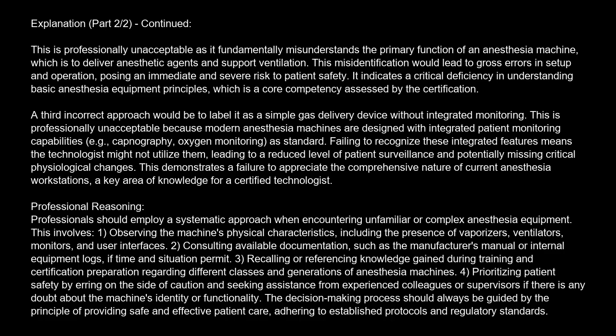integrated monitoring. This is professionally unacceptable because modern anesthesia machines are designed with integrated patient monitoring capabilities, e.g., capnography, oxygen monitoring, as standard. Failing to recognize these integrated features means the technologist might not utilize them, leading to a reduced level of patient surveillance and potentially missing critical physiological changes. This demonstrates a failure to appreciate the comprehensive nature of current anesthesia workstations, a key area of knowledge for a certified technologist. Professional reasoning.